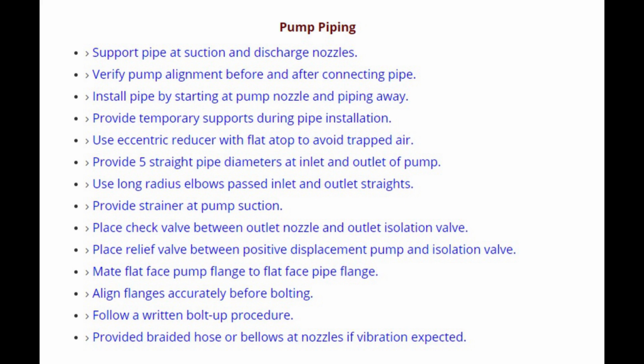Number 11. Mate flat face pump flange to flat face pipe flange. Number 12. Align flanges accurately before bolting. Number 13. Follow a written bolt-up procedure. Number 14. Provide a braided hose or bellows at nozzles if vibration expected.